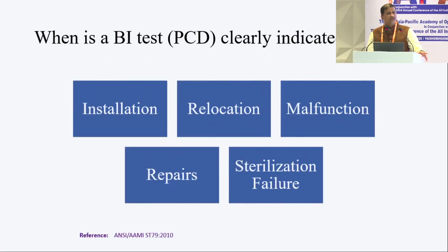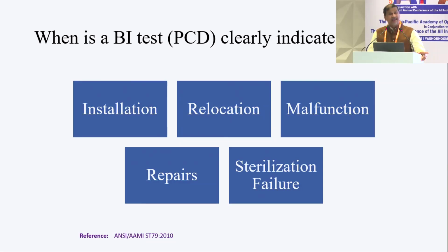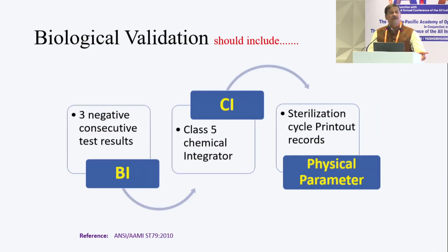So when is a biological test indicated? This is very important: during installation, relocation, after a malfunction, after you repair your autoclave, and in the event of a sterilization failure. So what should you do before you start using your autoclave? That is, if you buy a new autoclave or if it has failed and it's come back to you, 3 consecutive negative tests of the biological indicator with a class 5 integrator and a sterilization printout are all needed before you commission your autoclave. This is very important.